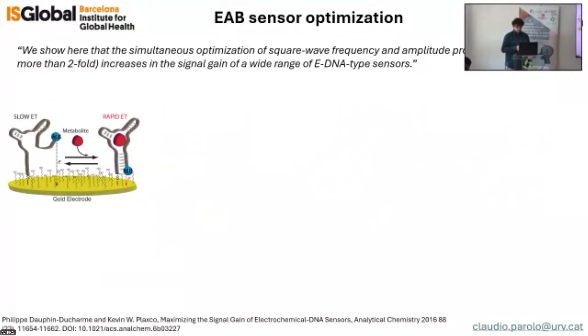It's not always the case, but if you are, let's say, lucky enough, you can get to a regime where you have signal off and signal on. That basically depends on the frequency and the amplitude that you employ. This work at the bottom explains really well how to optimize these 2 parameters and why they are important. Here, the blue areas are where you get signal off, meaning that the original signal is higher than after the addition of your target, and the red ones are signal on, meaning that the signal after the addition of the target increases.